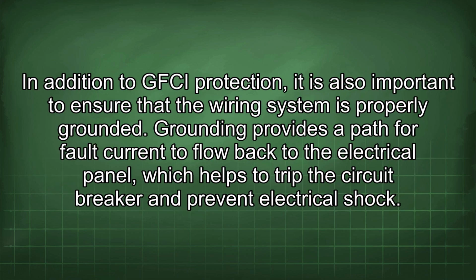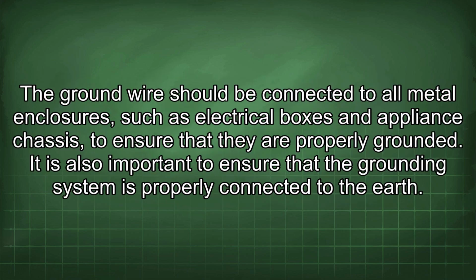In addition to GFCI protection, it is also important to ensure that the wiring system is properly grounded. Grounding provides a path for fault current to flow back to the electrical panel, which helps to trip the circuit breaker and prevent electrical shock. The ground wire should be connected to all metal enclosures, such as electrical boxes and appliance chassis, to ensure that they are properly grounded. It is also important to ensure that the grounding system is properly connected to the earth.